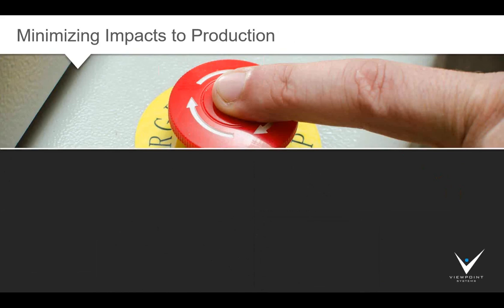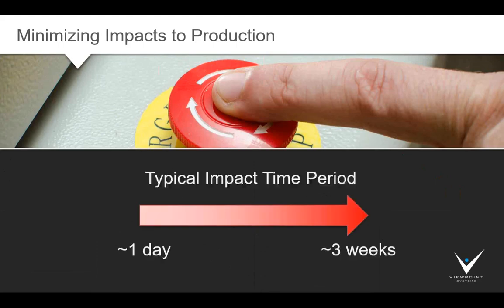In this scenario, you have to worry about the fact that you're going to be replacing the old system with a new test system, and you're going to want to consider what the impact is going to be to production. It'd be great if the old test system could be just removed quickly, the new test system put in place after connecting up some wires, you do a quick check of verification of the operation, and you're done in less than an hour. Oh, and by the way, the manufacturing supervisor doesn't even care because you did it over a shutdown. But in reality, production will be impacted.